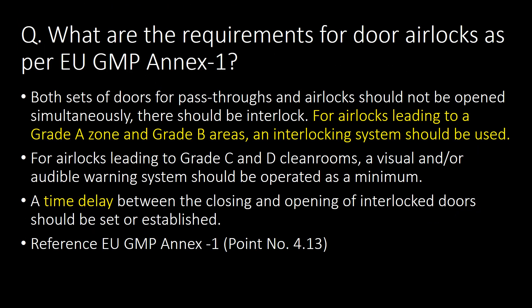What are the requirements for door airlocks as per EU GMP Annex 1? Both sets of doors for pass-throughs and airlocks should not be opened simultaneously — there should be an interlock. For airlocks leading to Grade A zone and Grade B areas, an interlocking system should be used. For airlocks leading to Grade C and D clean rooms, a visual and/or audio warning system should be operated as a minimum. A time delay between the closing and opening of interlocked doors should be established. Reference: EU GMP Annex 1, Point No. 4.13.